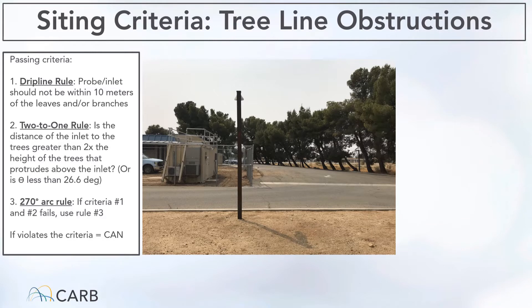Now that we know where our inlets will be located, we can move on to obstructions. There are sites that are surrounded by vegetation and trees, and those can grow over time. So it is a good idea to pay attention to obstruction. There are a couple of rules and criteria to follow to make sure your site is in the clear. There are three rules: number one, the drip line rule; number two, the two-to-one rule; and number three, the 270-degree rule.